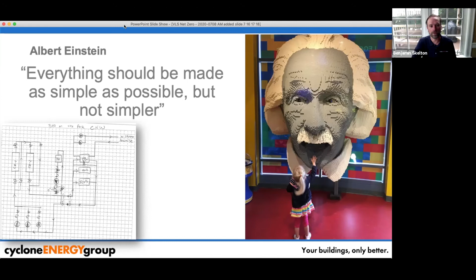really just prove too complicated either for the building operator or they just don't work the way that they were intended to work. They don't provide the same comfort levels. Things get overridden at the sake of comfort for energy efficiency, and it really starts with controls and overly complex control systems. I'm not a big fan of VAV or variable air volume systems. They've become the staple of office buildings and most buildings in the United States. And that's great, but they're moving air around. They seem like they're efficient, but there's much more efficient ways to handle building loads than moving large quantities of air and mixed volume. But the control strategies around VAV systems have gotten really, really complicated, and in our commissioning experience rarely work the way that they were intended to because they cause comfort issues.